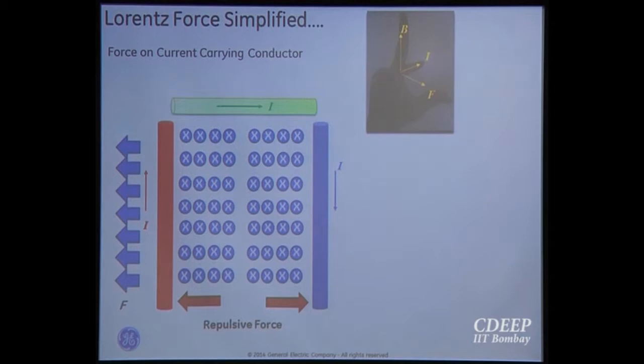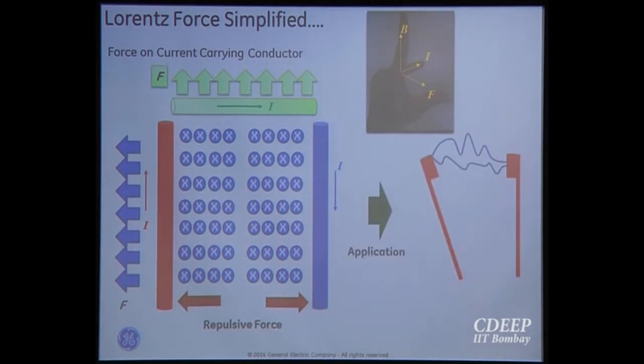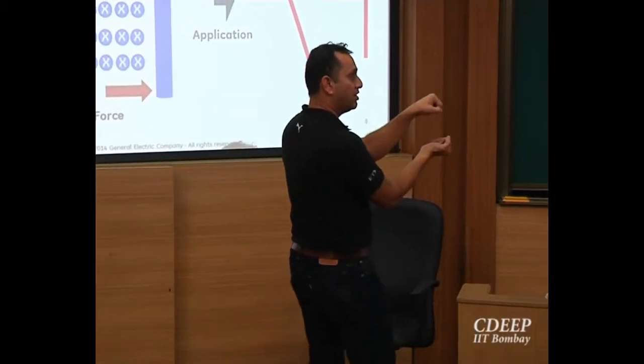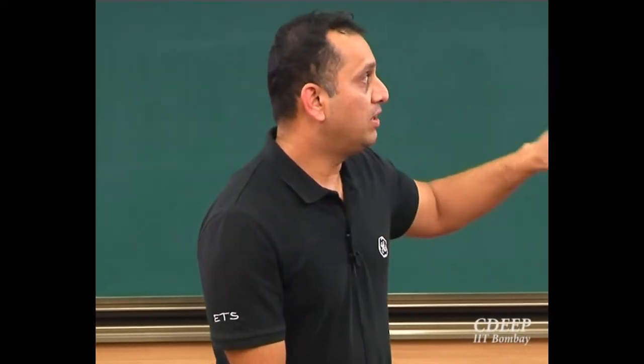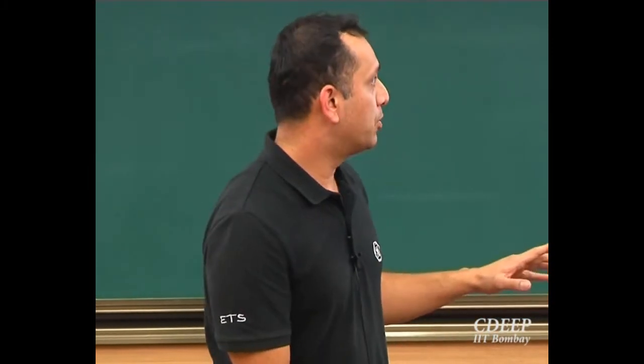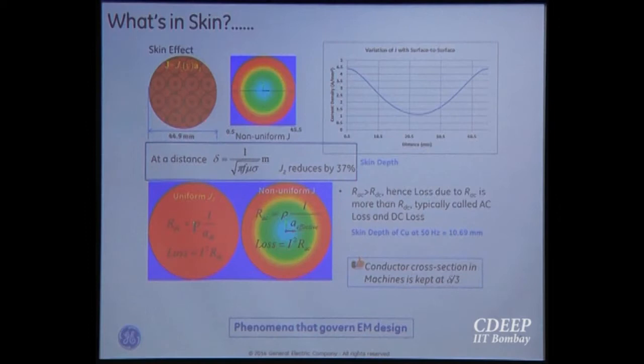Adding one more current bar on top, we can see the force acting on the horizontal wire going upward. We can implement this in circuit breakers. We have a fixed contact and a moving contact with a reverse current loop I1 and I2, with an arc in between. The objective is to design a circuit breaker such that it pushes the arc as fast as possible to the arc chutes. Our major objective is to quench the arc as early as possible.